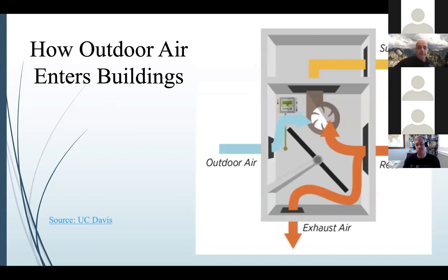So how does fresh air get into a building to begin with? This is a diagram of a typical HVAC unit that sits on top of a commercial building on the roof. Most of those package units have a little door on the outside of them, typically an economizer. And that economizer is what brings in fresh air. It mixes with outgoing air, and then it exhausts the difference out. So you can see fresh air coming in, it mixes with return air, and then the air goes out. It does an exchange rate of about 6 to 8 times per hour in a typical commercial building. Some of the naturally vented buildings work a little bit differently, but for the most part, probably 90% of the buildings out there, your typical package unit that's on your roof is what removes and supplies fresh air.